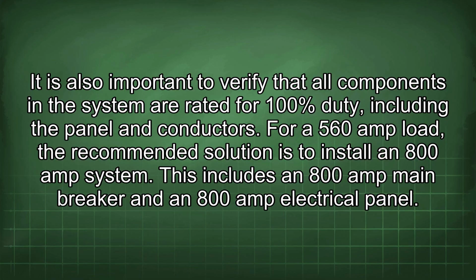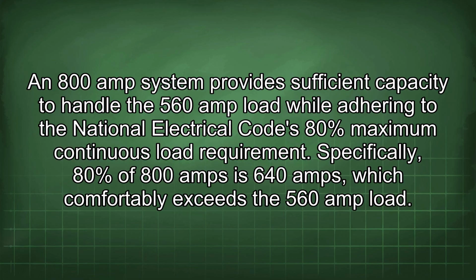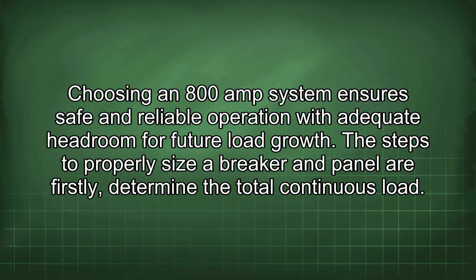This includes an 800 amp main breaker and an 800 amp electrical panel. An 800 amp system provides sufficient capacity to handle the 560 amp load while adhering to the National Electrical Code's 80% maximum continuous load requirement. Specifically, 80% of 800 amps is 640 amps, which comfortably exceeds the 560 amp load. Choosing an 800 amp system ensures safe and reliable operation with adequate headroom for future load growth.